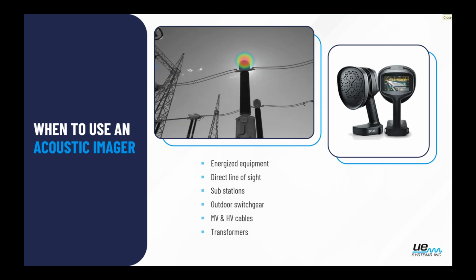So we're able to actually have that sound show up as a target. In this example, it almost looks like a thermal target or a weather map, but that's actually an origin point of ultrasonic frequencies. So we're still looking for the same thing, corona tracking, arcing, mechanical looseness, but we just have a built-in computer basically on this camera that's doing the work for us. It's analyzing it, it's targeting it, while it's still going to show sources of ultrasound. The part of having the computer built into it is that it actually can understand if this sound is actually electrical based or not, which is where the big benefit comes in for field inspections.